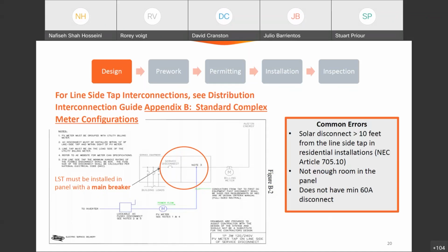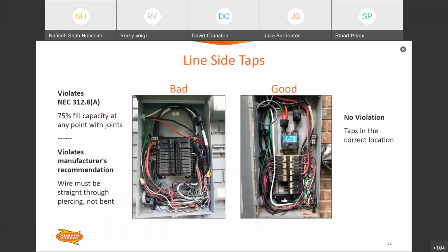That disconnect needs to be a minimum of 60 amps. So even if you've only got a 30 amp circuit that you're tapping, you still need a 60 amp disconnect enclosure. Whether or not you have to use something like fuse reducers, that's acceptable, but the enclosure itself needs to be rated for 60 amps, even on a circuit that doesn't require 60 amps. Alrighty, next slide.